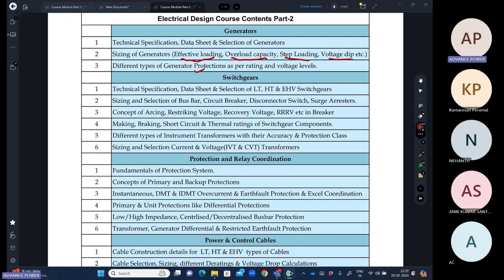So everywhere in motor, generator, transformer, I have written a protection, a single line. So basically, if you see, the protection and coordination are being listed here. So the protection which is not common to everyone, like motor, transformer, and generator, will be discussed individually. The protection which is common, like for a system, we are doing the primary or backup protection concept. Like backup is overcurrent and earth fault, and we are doing the coordination for overcurrent and earth fault. Then we are having a primary protection, which is also called a unit protection, like differential and distance protections.